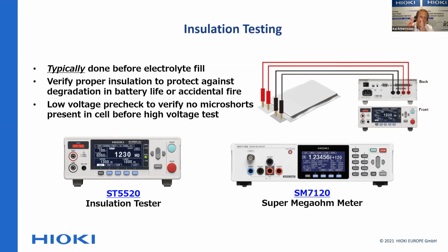So the proper insulation is absolutely crucial, absolutely critical. It not only protects against the degradation of the battery life, but it also protects against accidental fires, because you know what can happen if a lithium-ion cell starts to burn, starts to have a short circuit somehow, and that can have quite heavy effects. Everybody remembers the cells in, I think it was a mobile phone from Samsung, which started to catch fire in aeroplanes. One of the things in that case, I'm not sure if that was an insulation problem, but you could see the effects that a lithium-ion cell can have once it catches fire. Proper insulation is absolutely crucial to ensure that that doesn't happen.